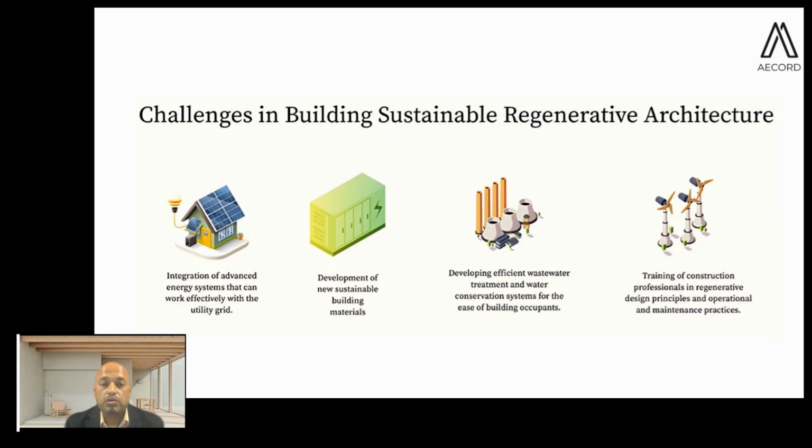So this is also one of the major aspects where we have challenges, because today most of the projects are not able to maintain their STP treatment quality, water treatment plants quality, output quality. So generally what happens is after some time, when you are not able to maintain it, you don't have the human skills and the technological skills to maintain it. You bypass it and you start taking tanker water instead of using treated water for landscaping and flushing and cooling towers in the HVAC cooling towers.